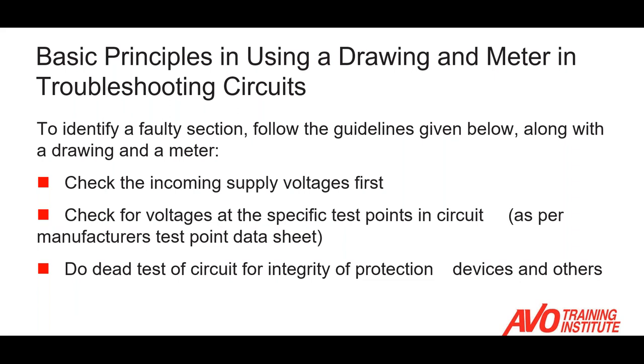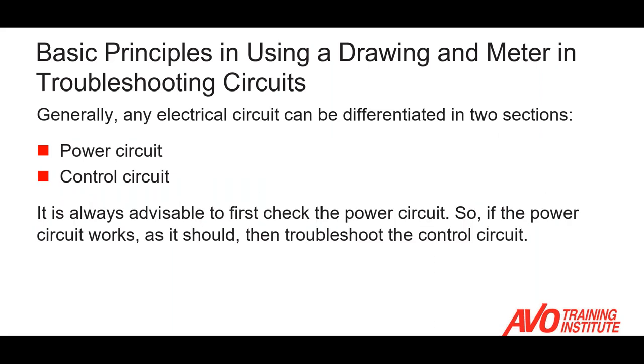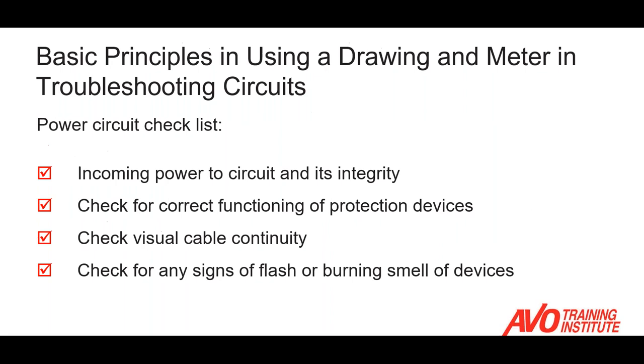We do a dead test of the circuit for integrity of the protection devices. In a dead test, or de-energized test, we want to check for continuity — we never want to check for continuity on an energized circuit. If it's not possible to perform the dead test, we need to connect the supply to the circuit and do a live test. Generally, our electrical circuits can be divided into two sections: the power section and the control section. It's always advisable to first check the power circuit; if that works as it should, then we can troubleshoot the control circuit.